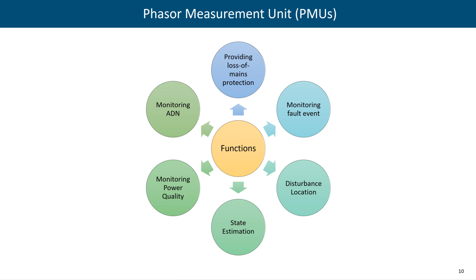Then phasor measurement units. These are becoming very essential, especially for the wide area monitoring system or wide area situational awareness system, because of which we are able to get the state of the grid. One of the main functions of the PMU is grid state estimation and disturbance localization, fault level monitoring, and providing loss of mains protection and monitoring power quality.